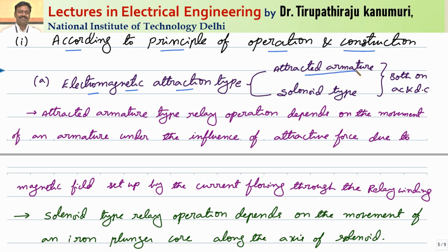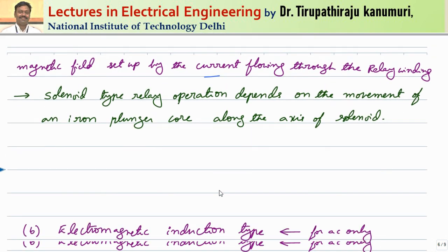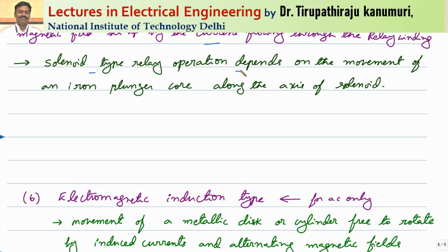The first one is the attracted armature type — whenever a coil is energized by a current, it will attract some iron bar. The second one is called the solenoid type. Both these types can operate for AC or DC. The attracted armature type relay operation depends on the movement of an armature under the influence of attraction force produced due to the magnetic field set up by the current passing through the relay winding.